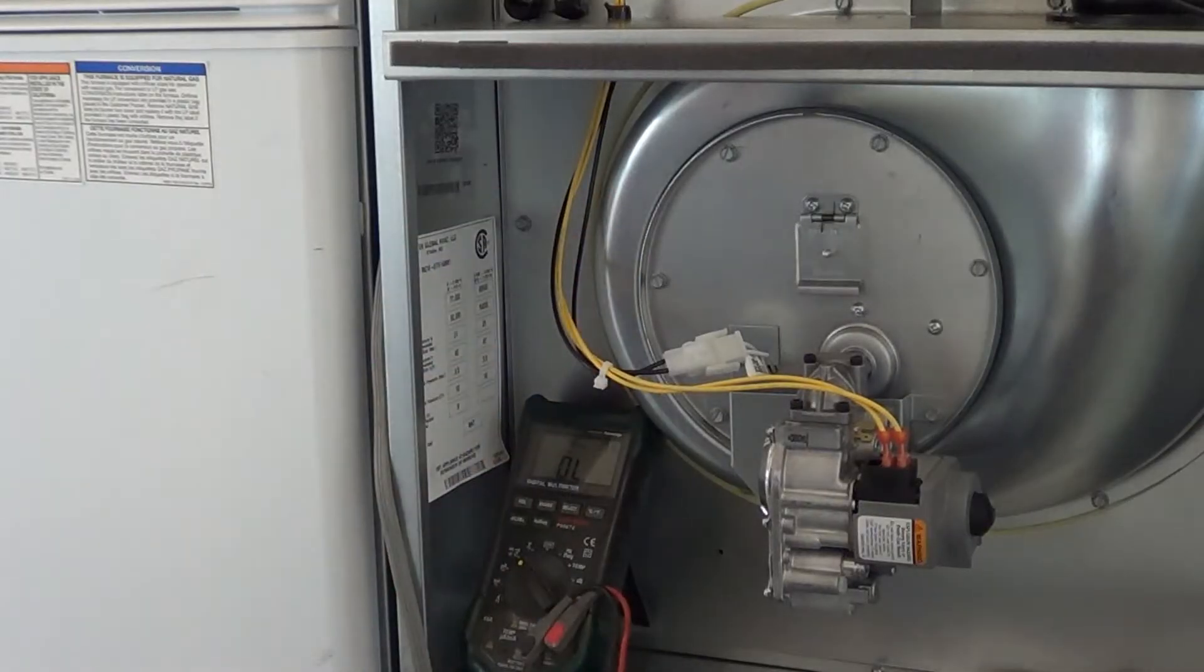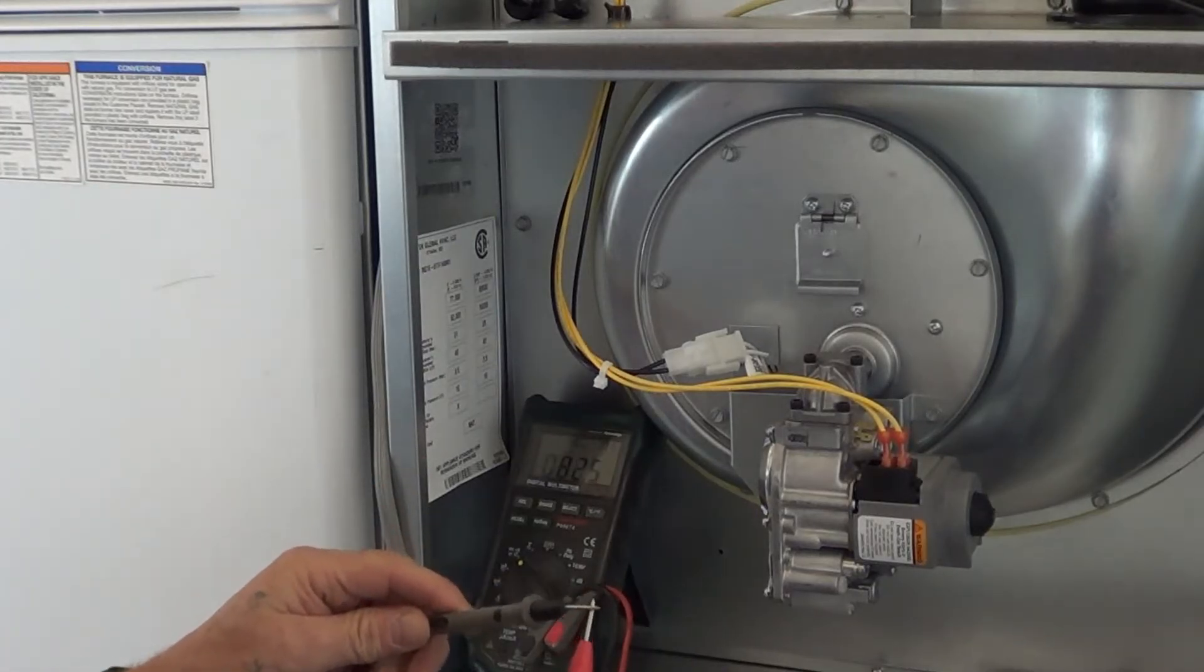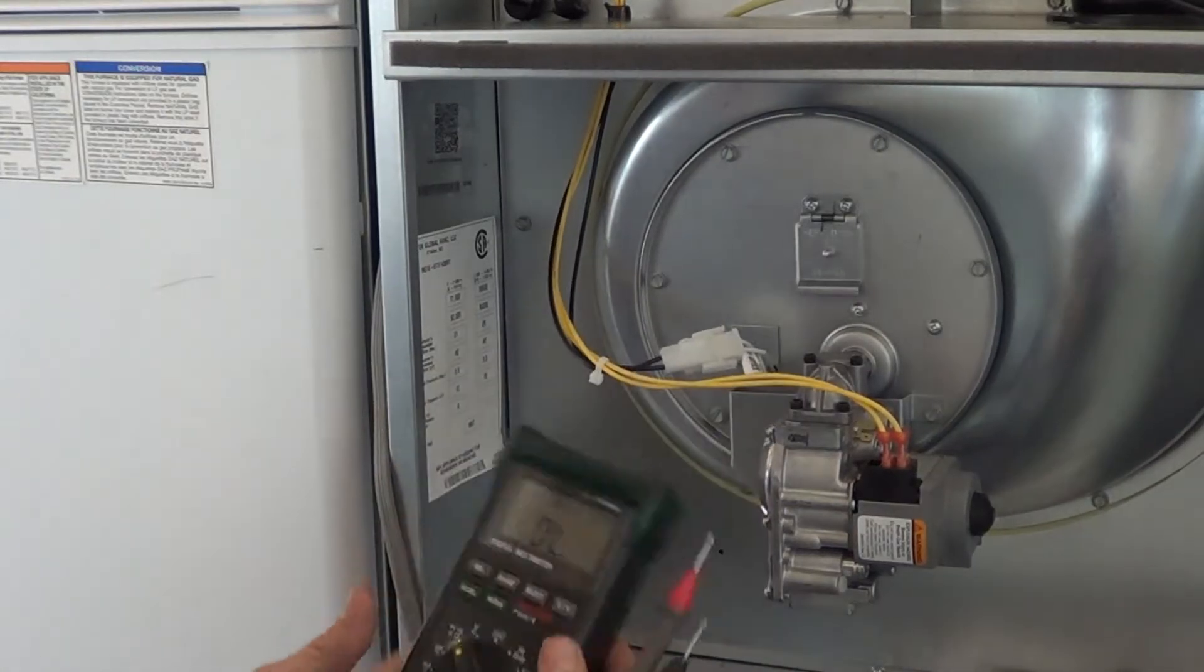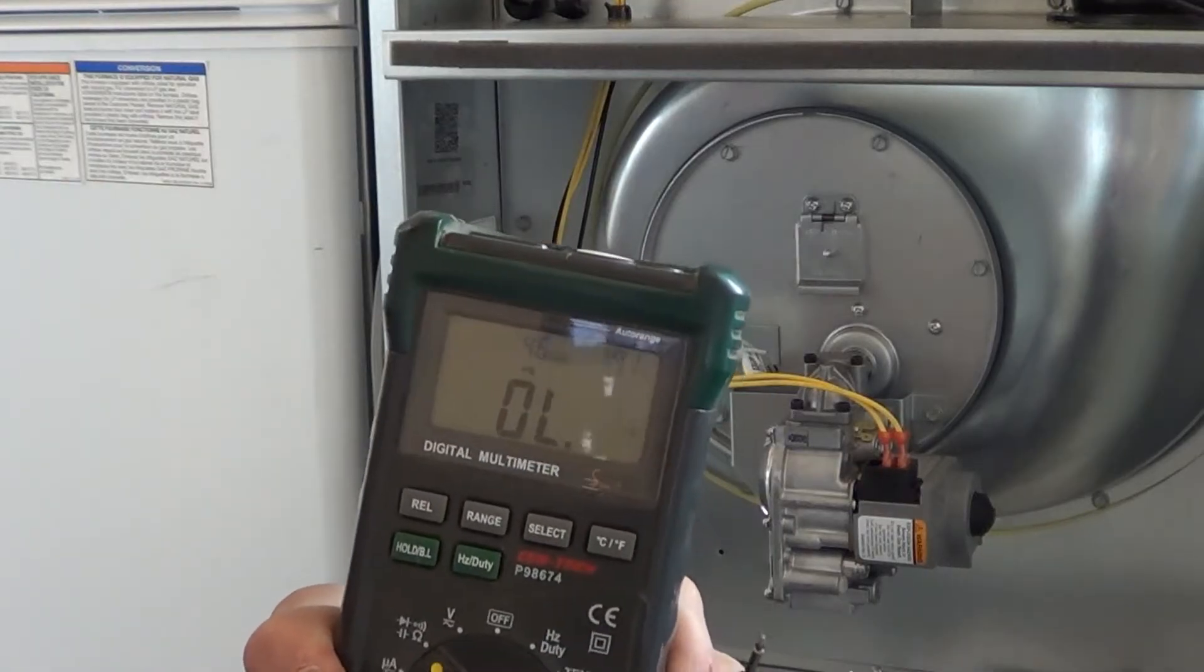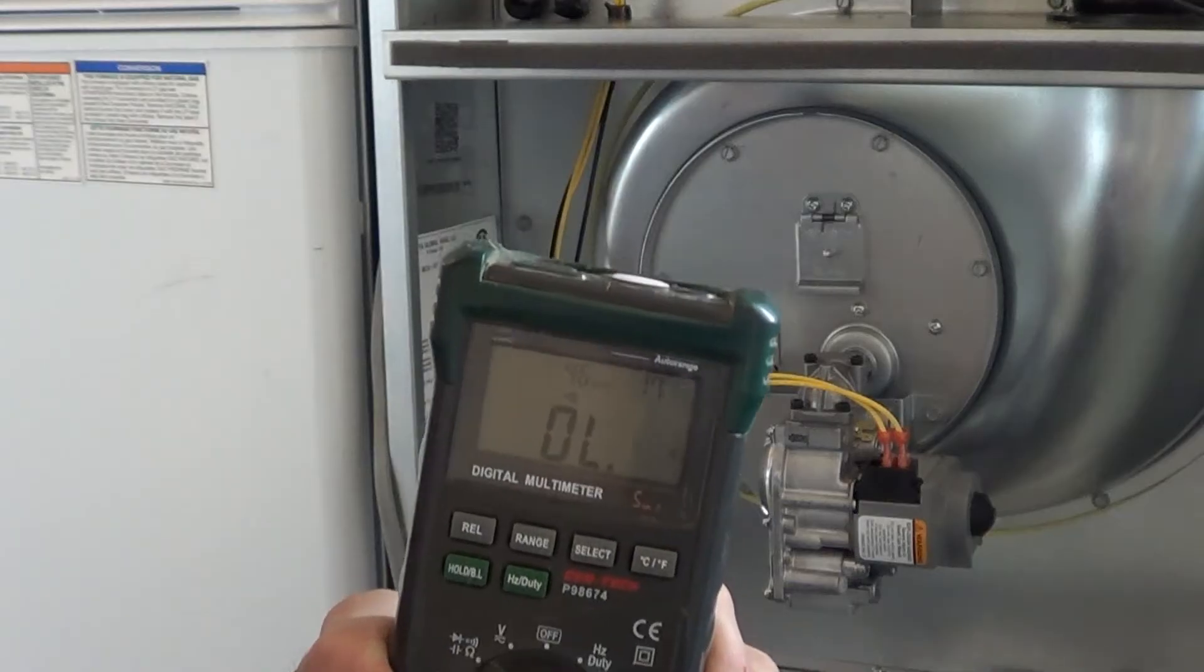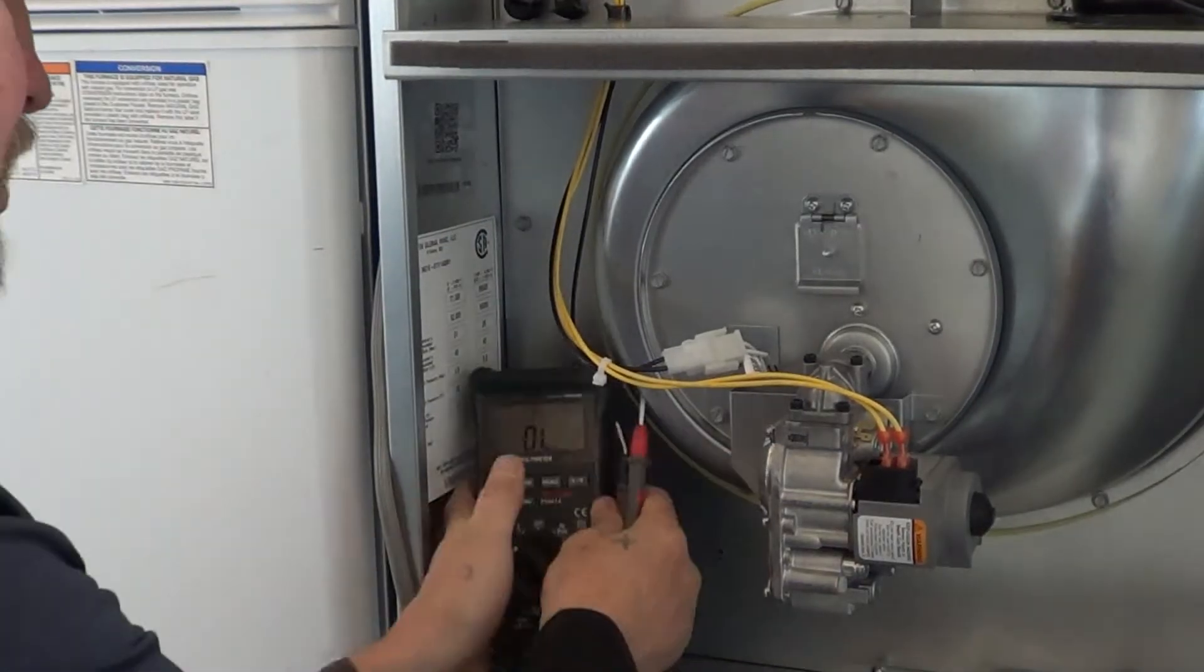To check for continuity, you get a tester that tests for continuity. I like to make sure mine has that little beeper on there. You definitely need a continuity tester to test the igniter. It's going to show some resistance there, and we're going to set this over here.